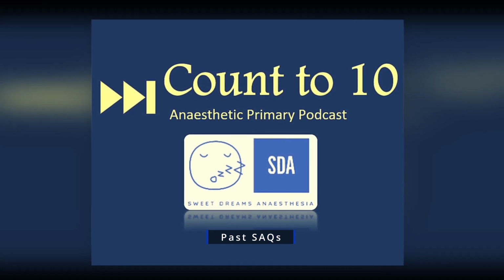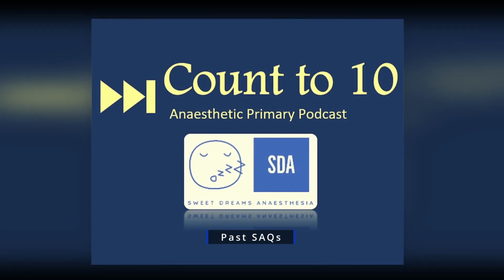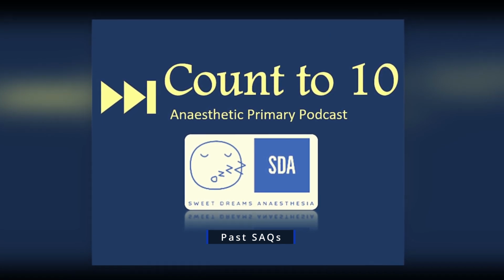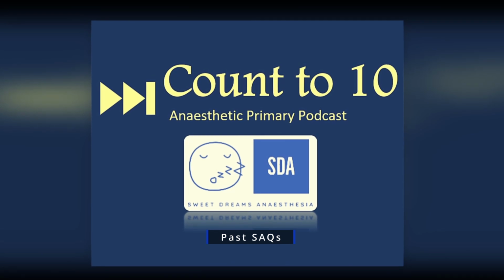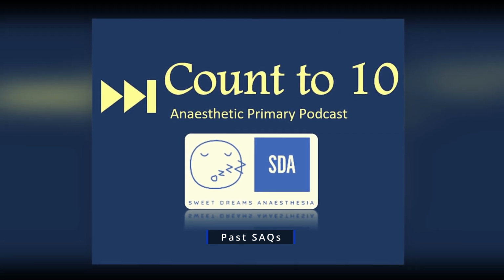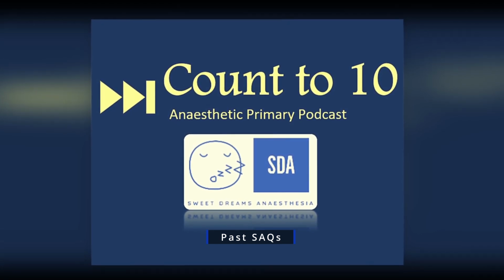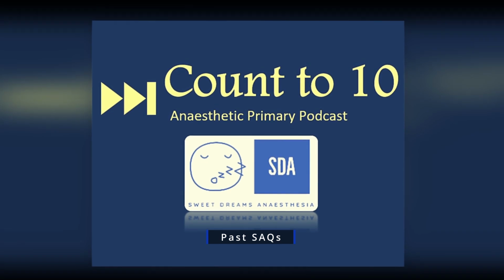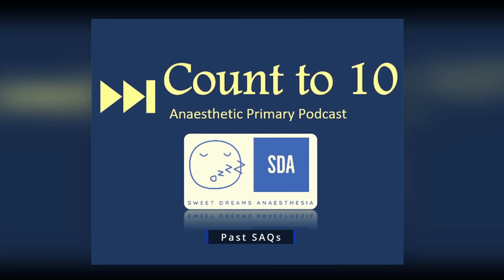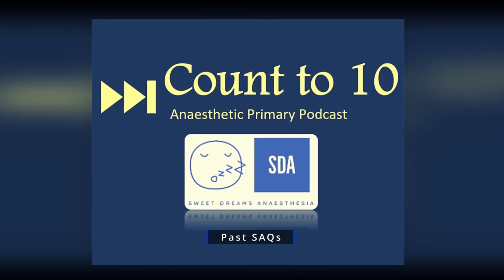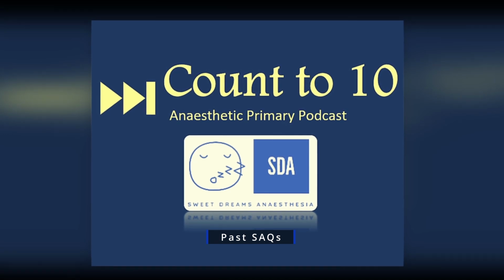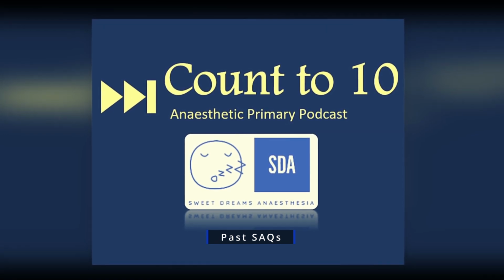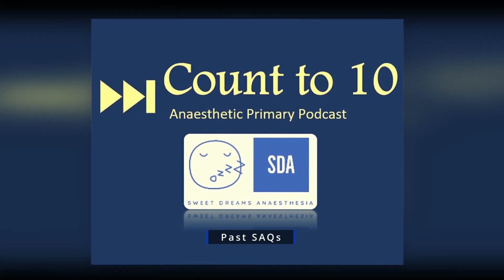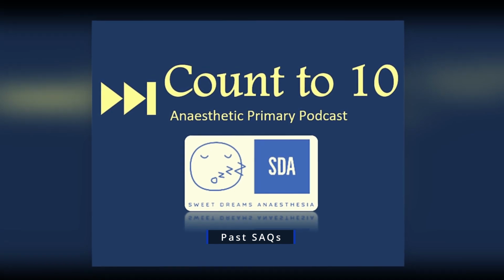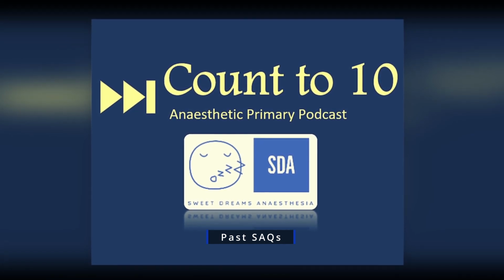Therefore, there's a sensor, an integrator, and an output. Each part of the components has a specific role to play in this pathway. The tubing and the normal saline allows for hydraulic coupling, therefore energy is not lost before it gets to the transducer. The transducer has incorporated Wheatstone bridges and strain gauges, which change resistance based on change in pressure.